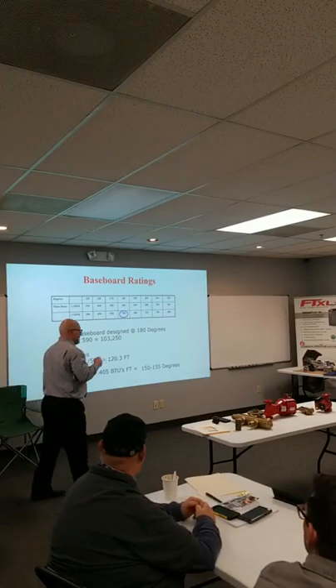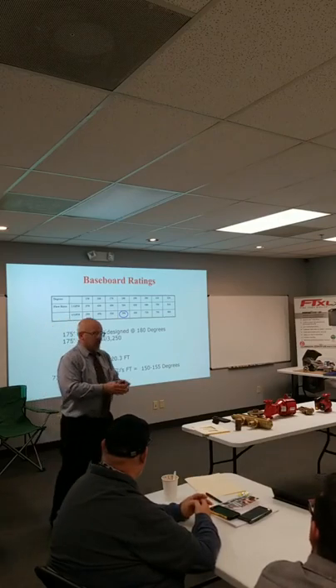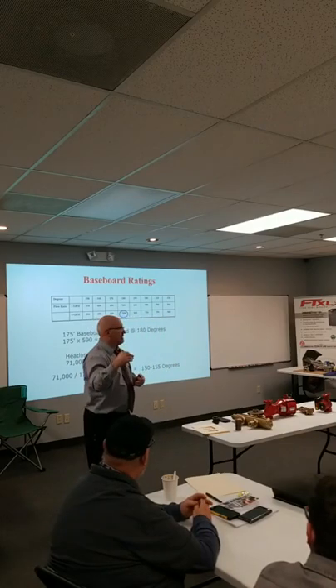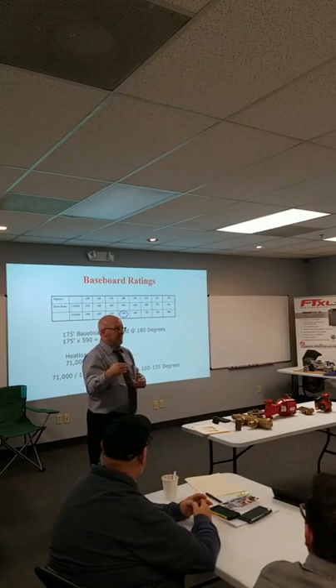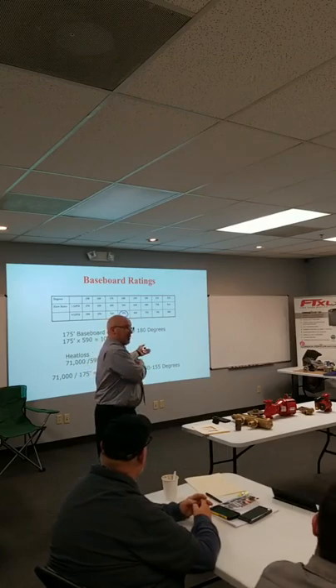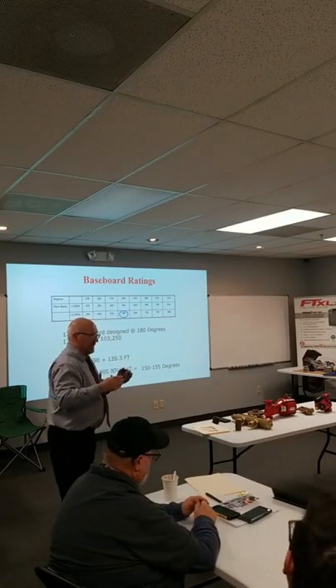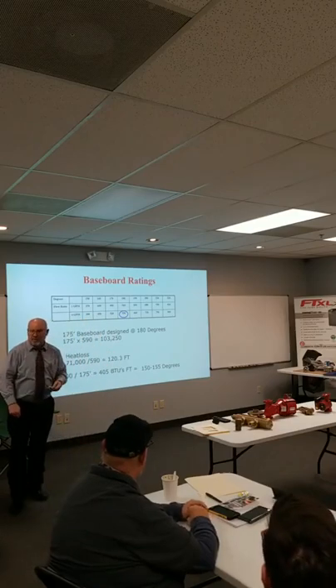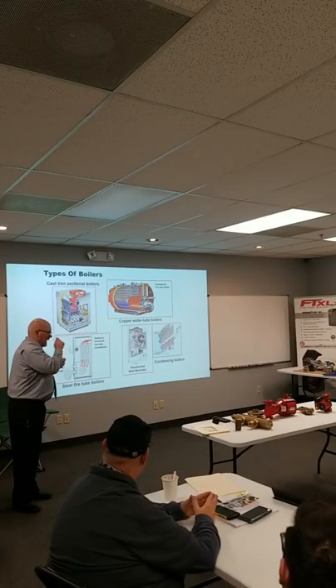And guys, what I like to do is a heat loss at my design temperature of, say, 0. Also, I like to do a heat loss at 60 degrees outside, because I still might get a call for heat. Now I'll know what my minimum firing rate needs to be with that boiler. So I know the range. I'm going to be able to take care of the worst case scenario, but I don't want it short cycling in the best case scenario. I don't know if that's the right term to use for those two figures, but do you get what I'm saying? All right, so we talked about that would be why we would do condensing.